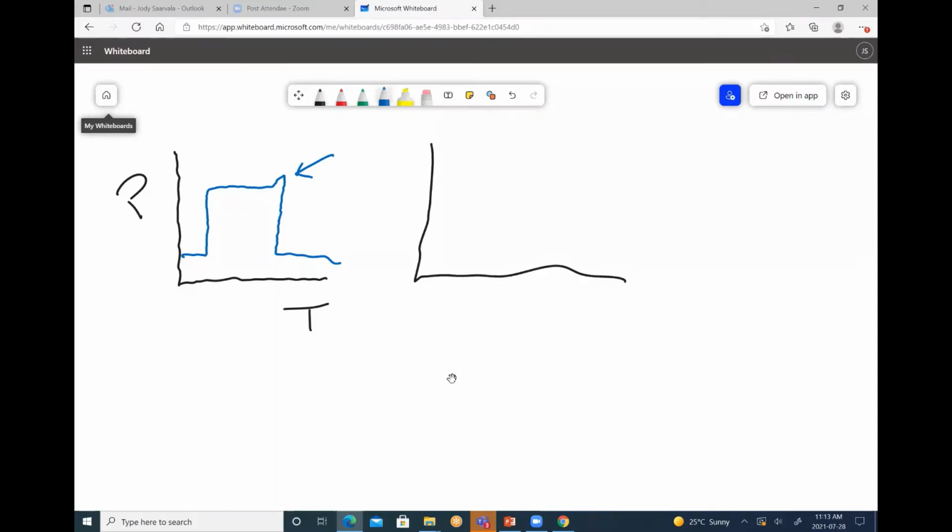And what you might see on your flow waveform for pressure control, again, forgive me for the squigglies, if your I time is too long, so this is flow and this is time. Our flow starts at 0, say I'm right on top. Our flow goes up and it degrades down.